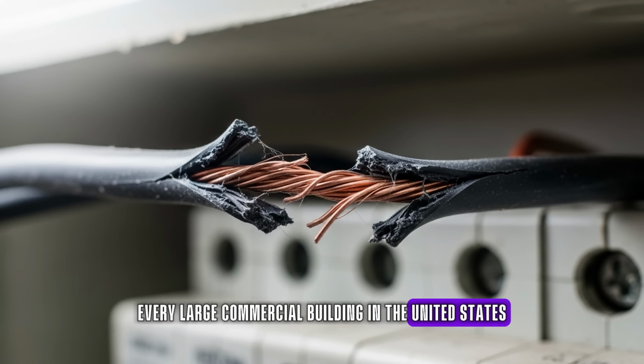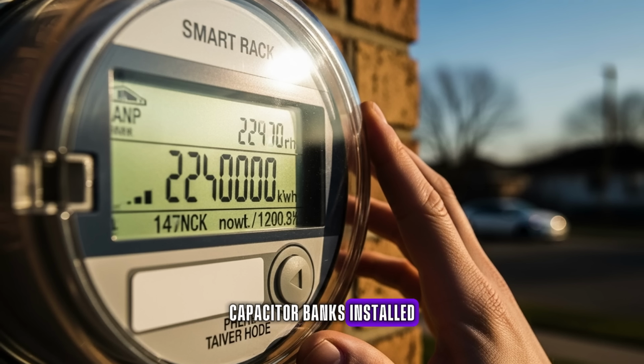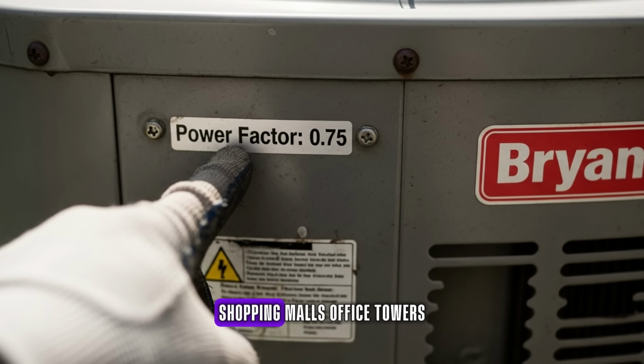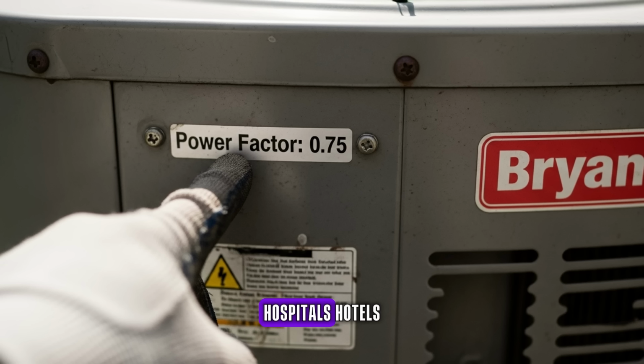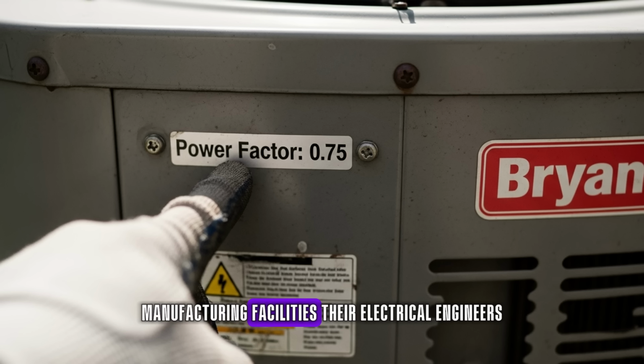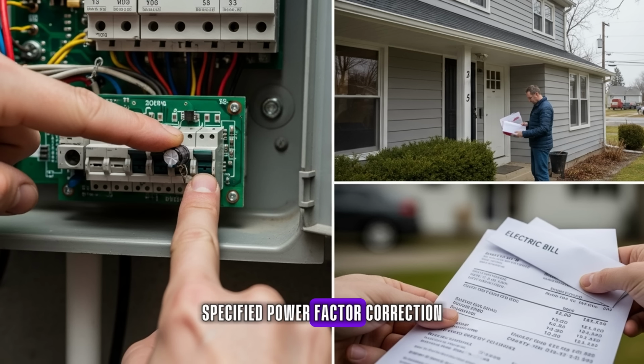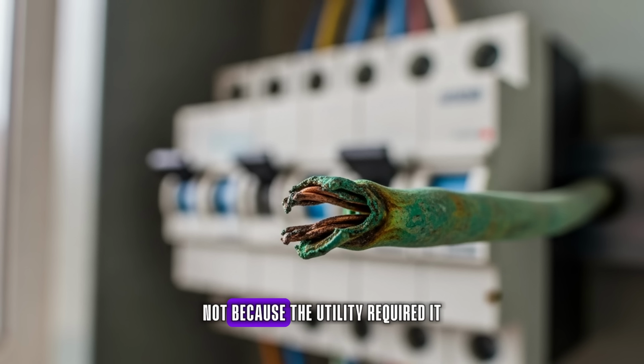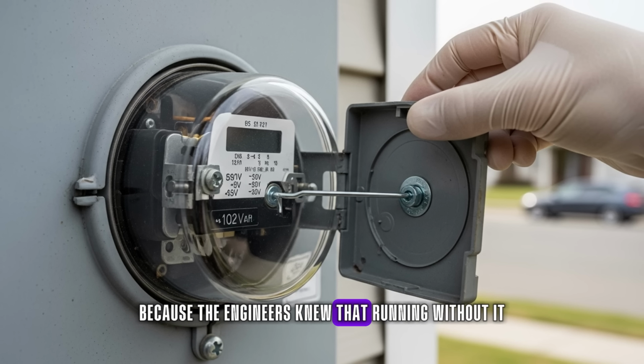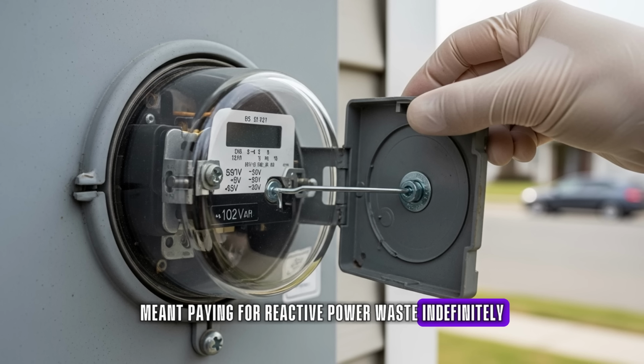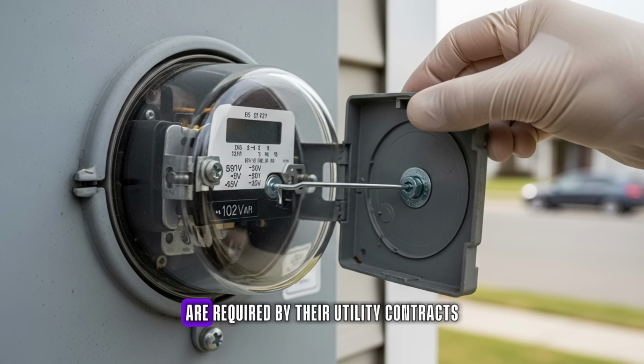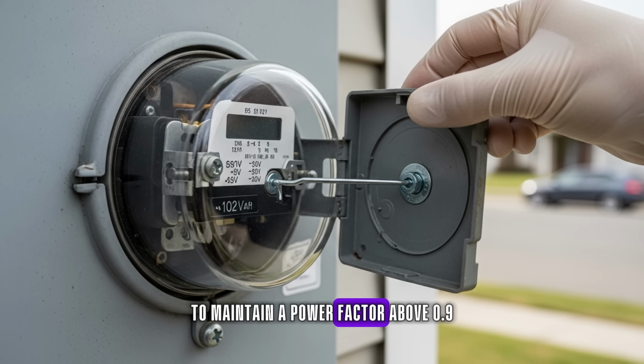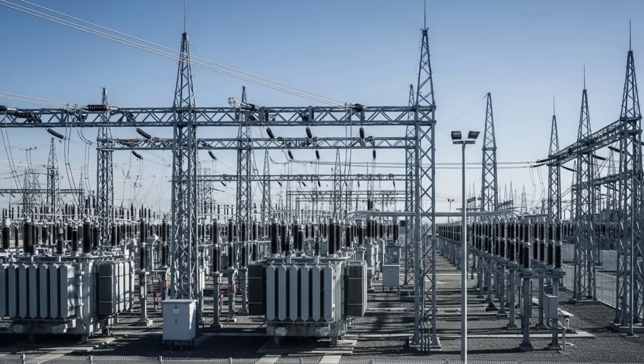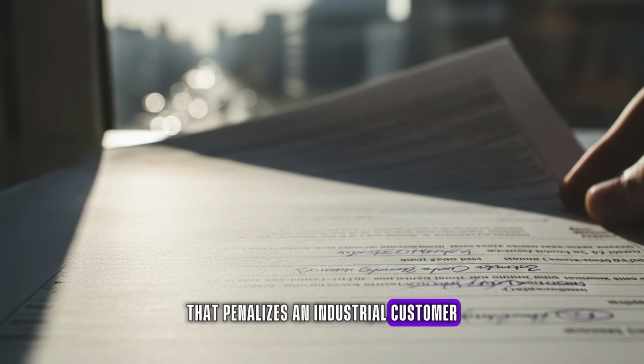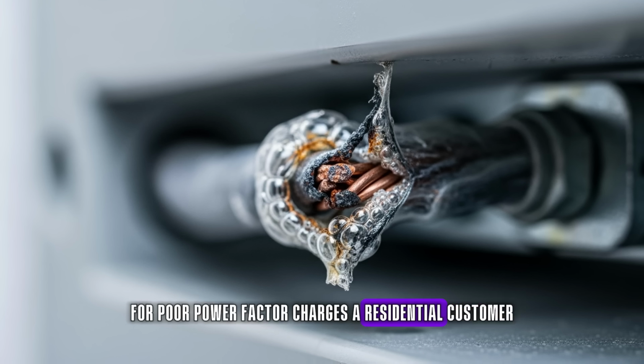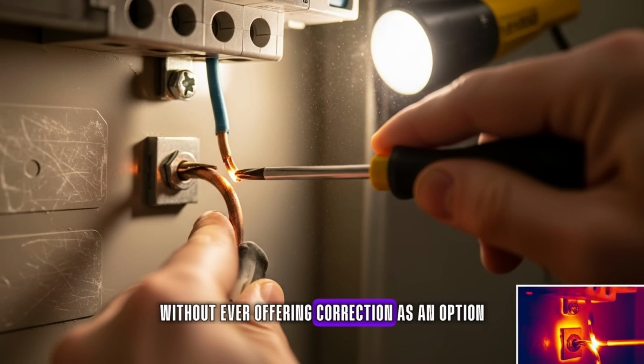Every large commercial building in the United States has power factor correction capacitor banks installed as standard electrical infrastructure. Shopping malls, office towers, hospitals, hotels, manufacturing facilities. Their electrical engineers specified power factor correction on day one of the building design, not because the utility required it, but because the engineers knew that running without it meant paying for reactive power waste indefinitely. Industrial facilities with large motor loads are required by their utility contracts to maintain a power factor above 0.9 or pay a penalty surcharge. The same utility company that penalizes an industrial customer for poor power factor charges a residential customer for the reactive power waste without ever offering correction as an option.